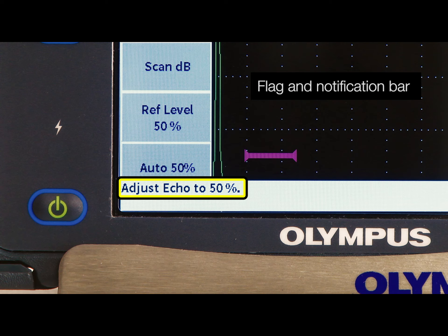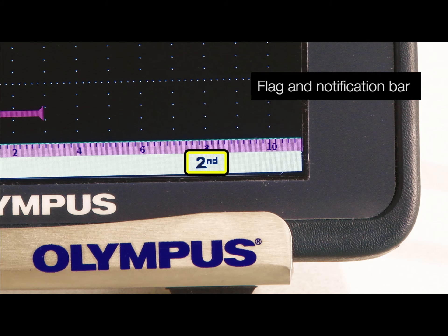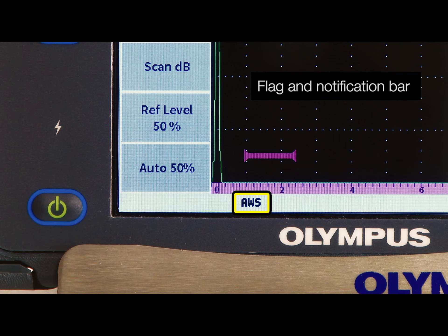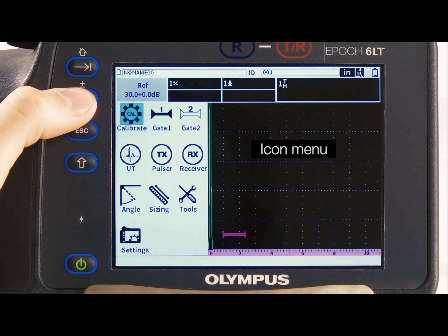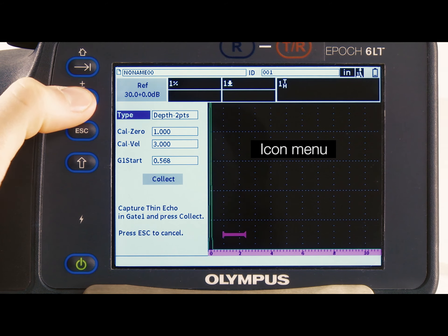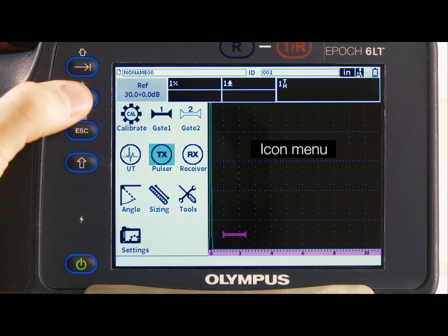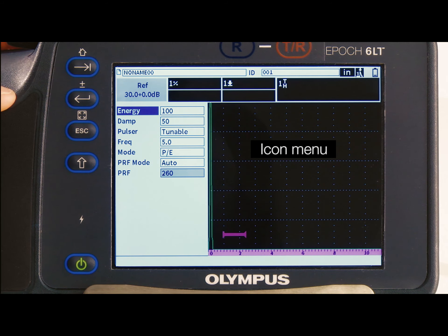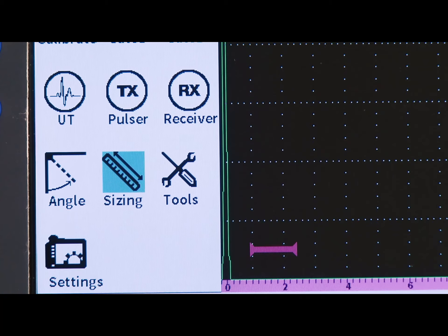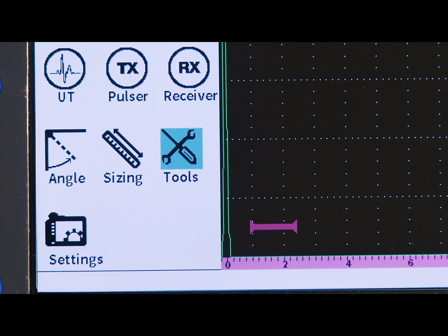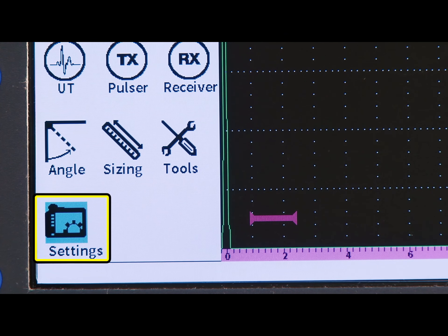At the bottom of the screen, there is a flag and notification bar. This indicates which functions are active and displays the instrument errors and important notifications. The setup mode's icon menu enables users to calibrate the flaw detector, adjust their inspection setup, and view a complete list of instrument settings by selecting the settings icon.